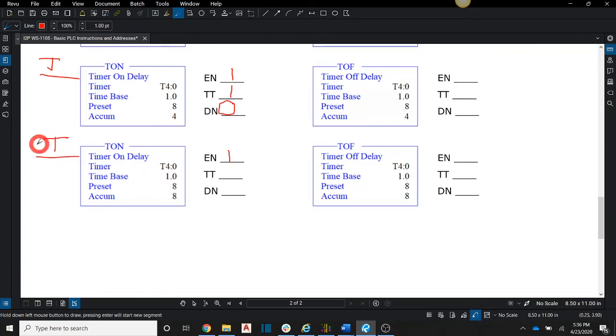Now this rung could have been on for longer than 8 seconds. It could have been on for 2 hours. But our timer, once it reaches the preset value, it just stops timing. Well, when it stops timing, my timer is no longer timing. My timer timing bit gets set to a 0. Now, our definition of complete is when preset and accumulated equal each other.